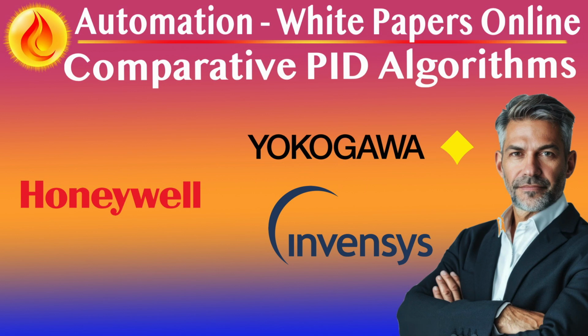Yokogawa supports both ideal, interacting, and parallel, non-interacting PID structures. This enables either intuitive, predictable tuning, ideal, or independent term adjustment, parallel, although parallel tuning can lead to unintended effects if gain interactions are misunderstood. Engineers must choose the form explicitly during function block configuration, giving them granular control over loop behavior.